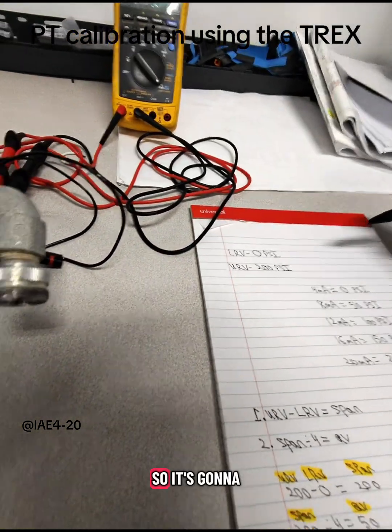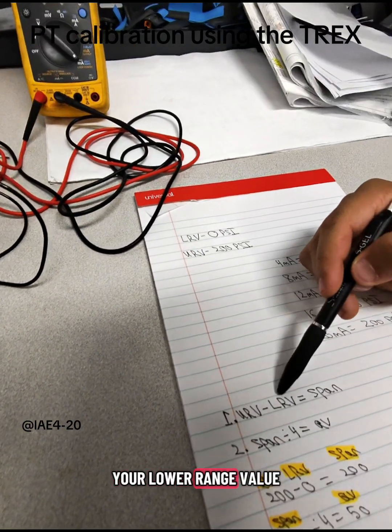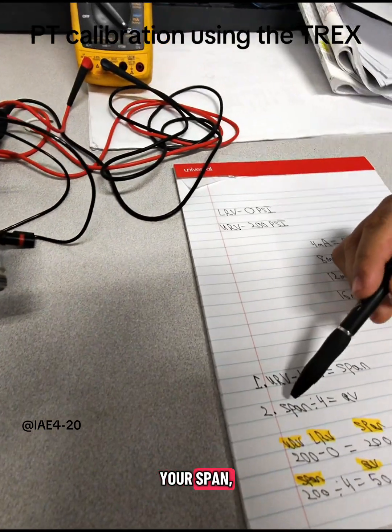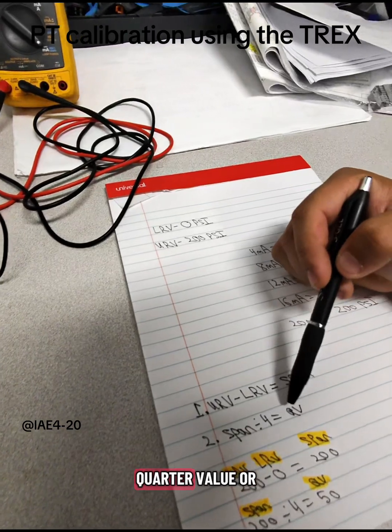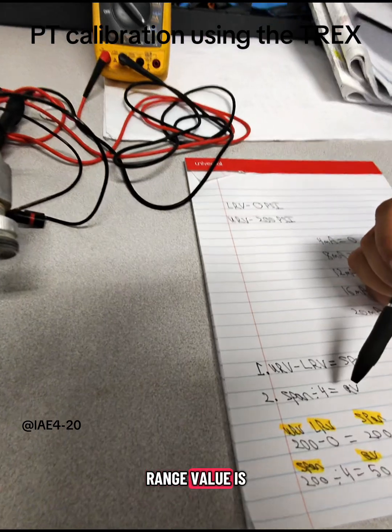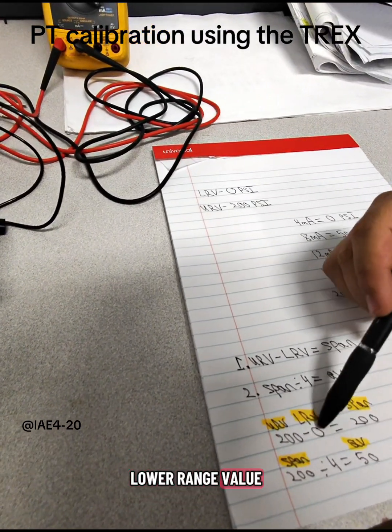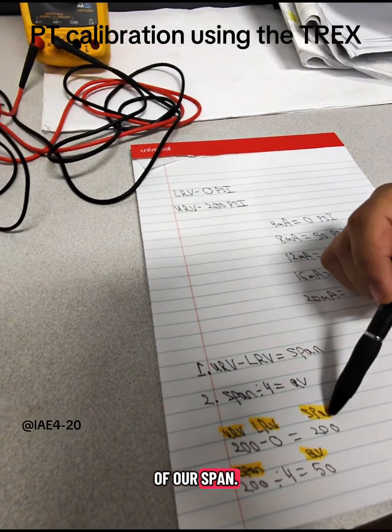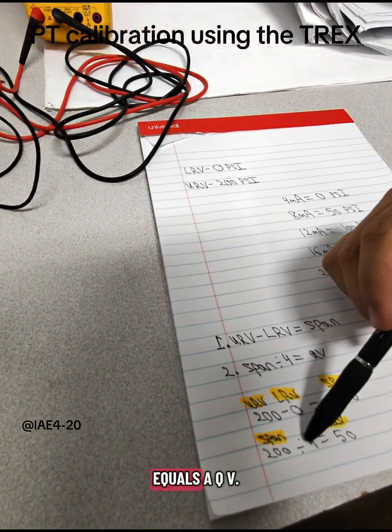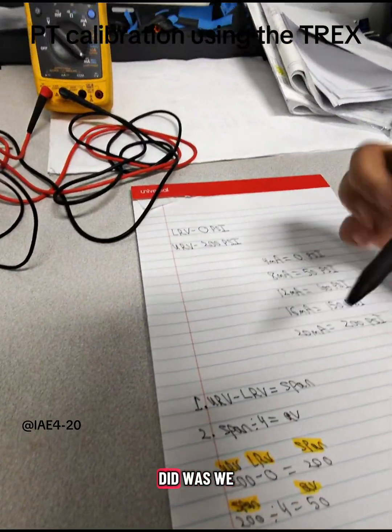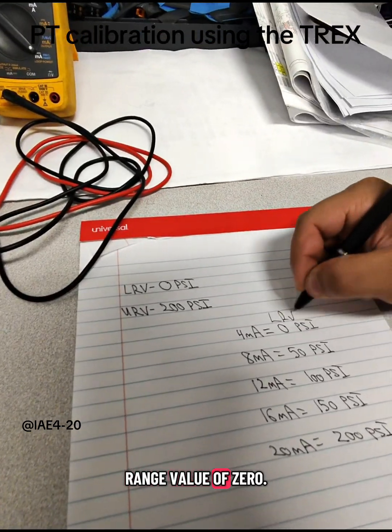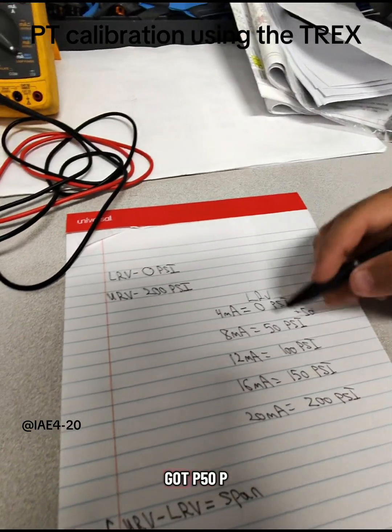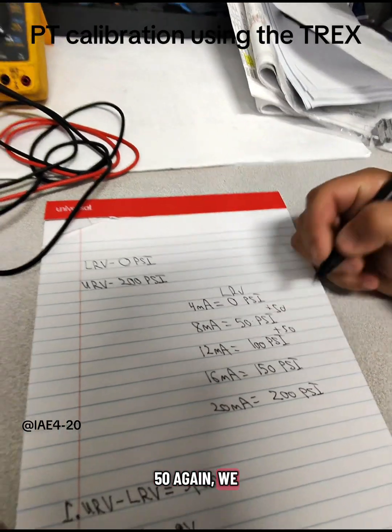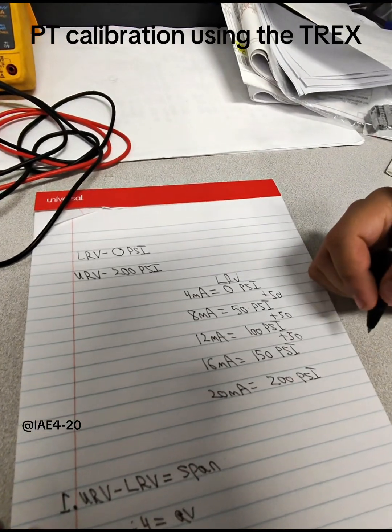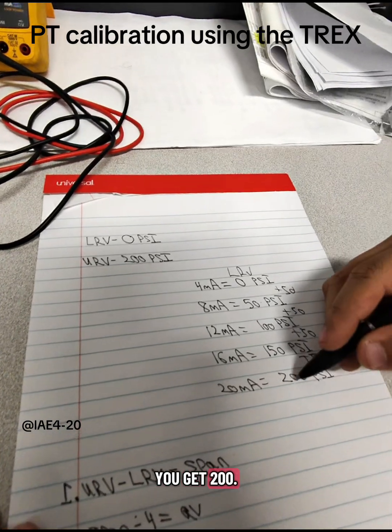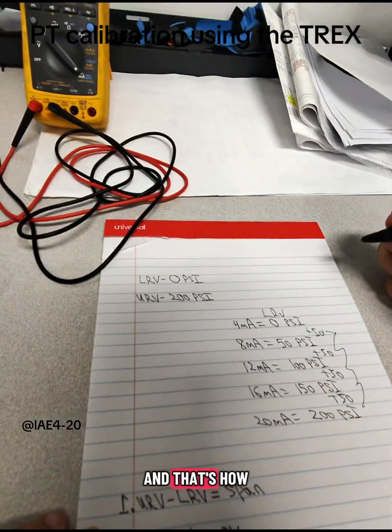And I'm going to take you through the math I did to get these values for a 5-point check. So it's going to be your upper range value minus your lower range value equals your span. Then you grab your span, divide that by 4, and it gives you your quarter value, or your QV. So our upper range value was 200 minus our lower range value of 0 equals 200 of our span. Our span, which is 200, divided by 4, equals a QV of 50. So then what we did was we had a low range value of 0. We just added 50. So we got 50 psi. Then we add 50 again. We got 100. Add 50 again, 150. And add 50 to 150 and you get 200. So you're adding it 4 times. And that's how you get your 5-point check.